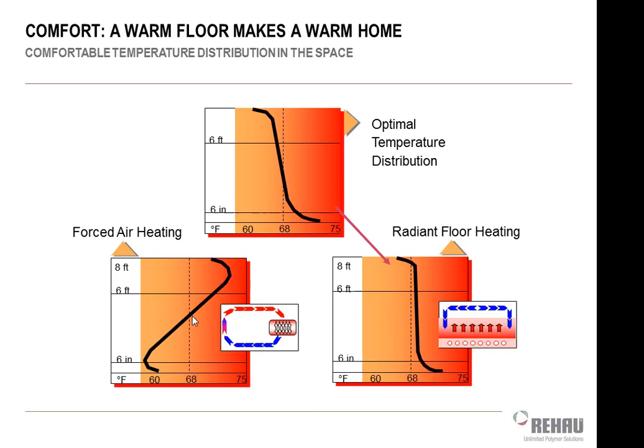The radiant floor works the exact same way. The radiant floor is literally shining on the occupants with infrared heat, and they're feeling warm because of that, which means that the air temperature in the space can actually end up being lower, and they're still going to feel comfortable. But the air temperatures, because we're not heating the air directly, are very even. So this chart's here showing you a radiant floor system from 6 feet to 6 inches being a fairly consistent temperature up and down.